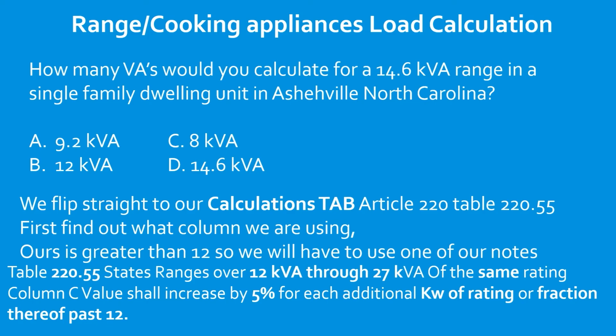So note 1 says for ranges that are over 12 through 27 of the same rating. So we could have more than one range, but they're all of the same kVA rating, okay? In this case, we only have one range, so it's of the same kVA rating. So what we're going to do is increase the column C value by 5% for each kilowatt rating past 12 or major fraction thereof. And I'm going to explain what that means.